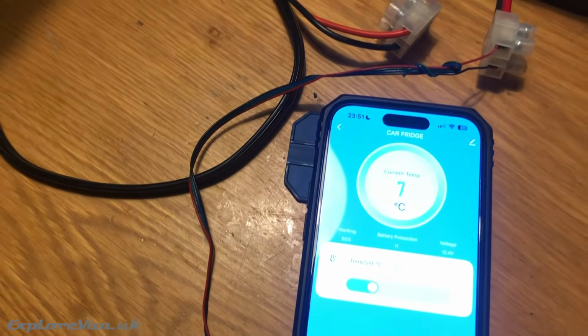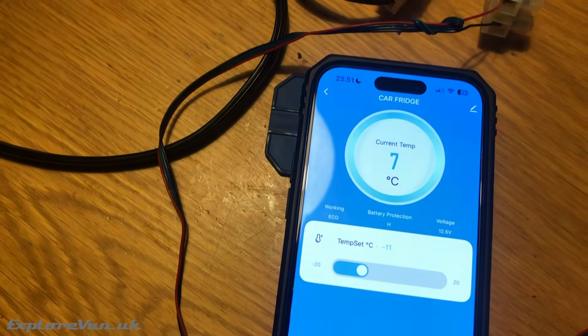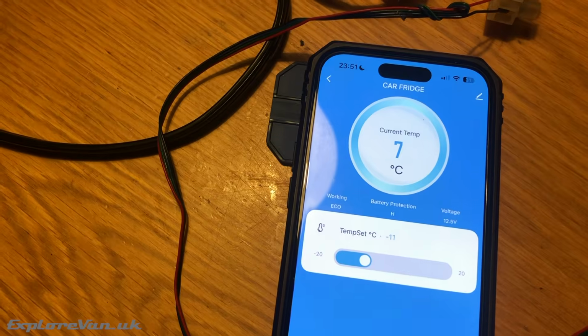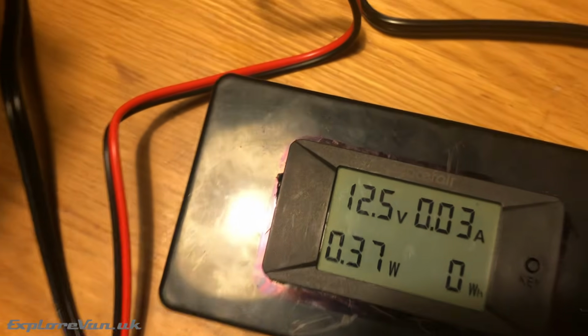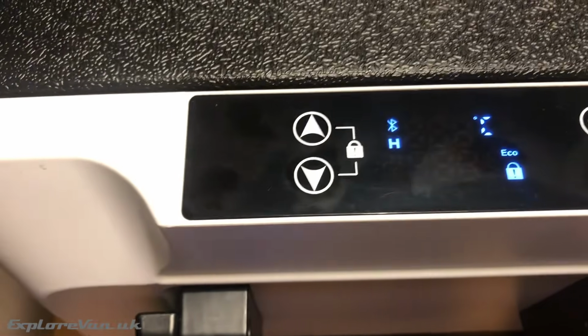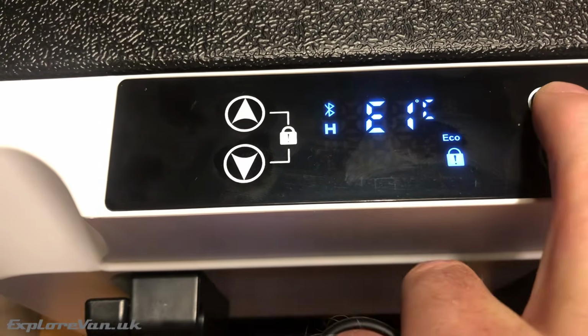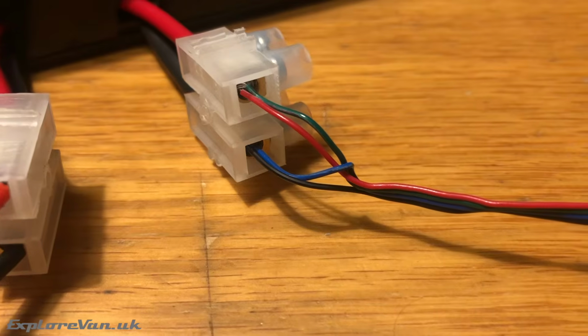Because that voltage is being lost in the cable when it's under load, the healthy reading at the power pack or battery is what often causes the confusion in why the fridge has shut down. It's not that the battery is low, it's that the voltage at the fridge is too low because of the cable.